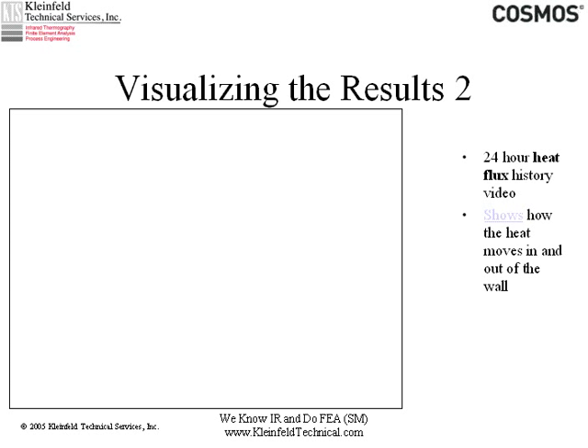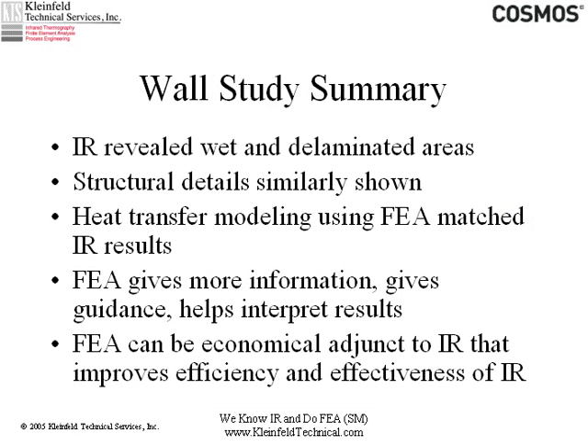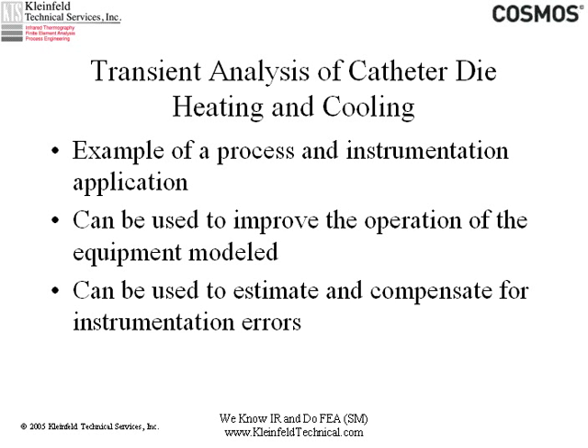What we found from the wall study: the IR worked as hoped based on our understanding of the physics — it revealed wet and delaminated areas. Structural details were also shown where the ends of floors meet the exterior wall, adding more mass that can absorb heat — the same as how the wet areas work, absorbing heat differently because they've got more thermal mass, resulting in less temperature swing. We found that heat transfer modeling using the FEA approach matched the infrared results, gave us more information, gave us guidance, helped us interpret the results, and it's an economical adjunct to the infrared as it would be to pretty much anything else you want to do.